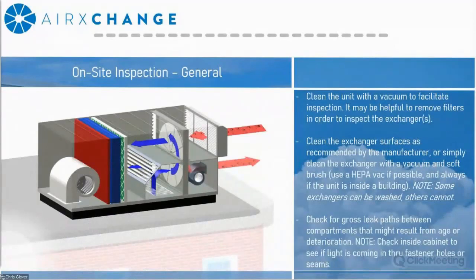Okay, so start the inspection of the system. You're going to want to clean the unit with a vacuum to help facilitate the inspection and allow you to see areas where there may be potential for leakage. You're also going to want to clean the heat exchanger surface area as recommended by the unit manufacturer. I'll go over Airxchange's cleaning methods shortly. The two most common methods are using either a vacuum or washing the material with soap and water. And once again, I will include a section on how we perform that on Airxchange wheels.